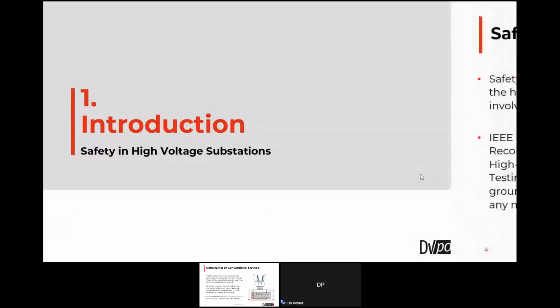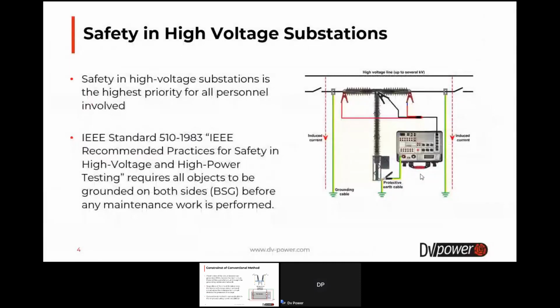The main reason for testing a high voltage object under both sides grounded condition is safety during maintenance and testing in a high voltage substation. I hope you can see my screen. Safety in a high voltage substation is the highest priority for all personnel involved. The IEEE standard recommends all objects to be grounded on both sides before any maintenance work is performed on the test object, in this case, the circuit breaker.